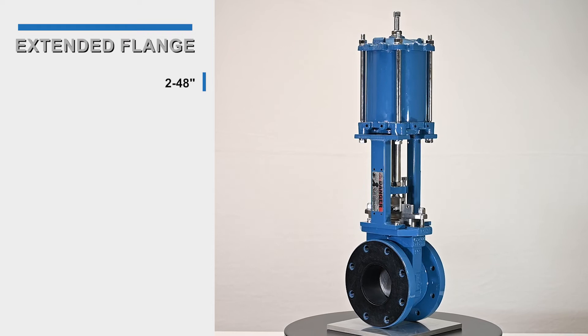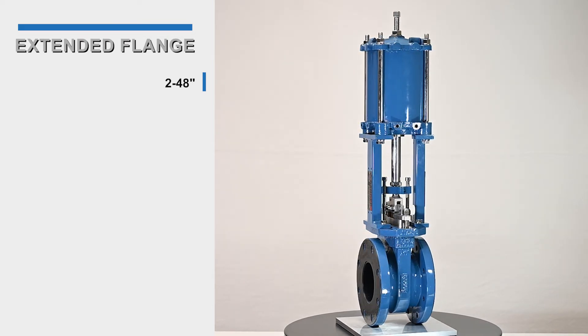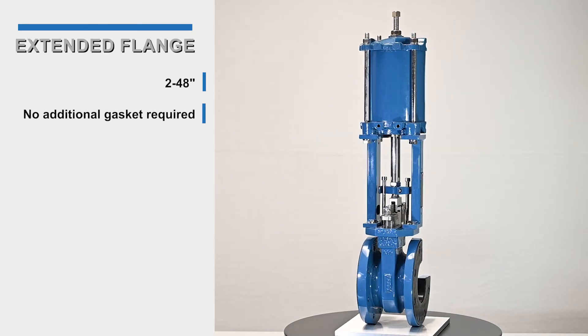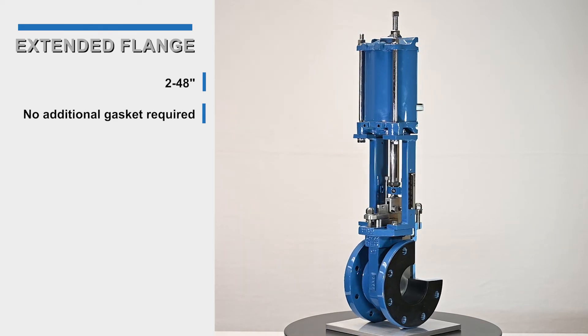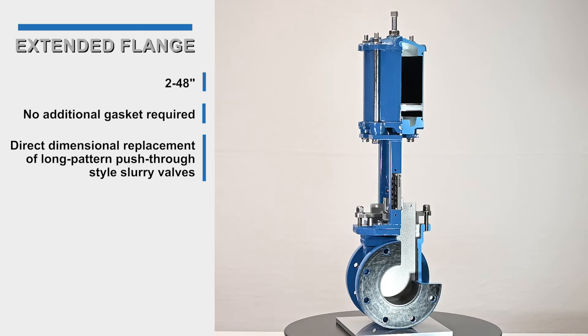The DeZURIK extended flange KUL body configuration is available in 2 to 48 inch sizes. The urethane liner wraps around the entire flange face, providing a flat faced sealing surface typical to the slurry push-through valve. The valve body is a direct dimensional replacement to the long pattern push-through style slurry valves.